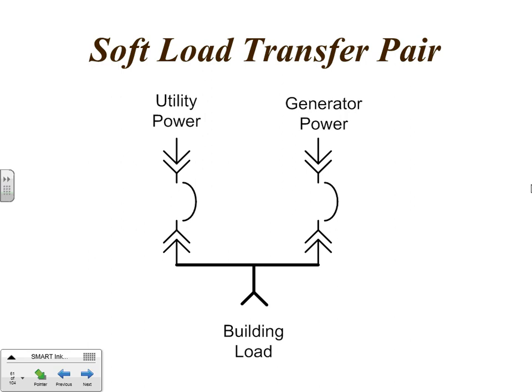Yeah, that requires an entrance rating for this device, and is primarily on the utility side. This becomes an entrance rated breaker, so it'll be service entrance rated. And again, then the load is in the entire building. And that's the most common place we see the soft load switches, and when we're taking over the whole facility. So this is a service entrance device as well. However, we have seen them in distribution where we've had critical load that the owner's been concerned with, so it doesn't have to be entrance rated at that point.